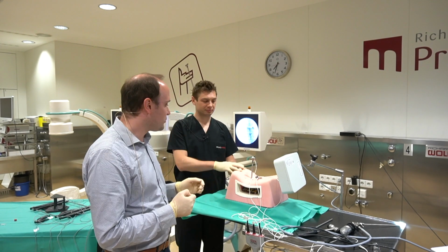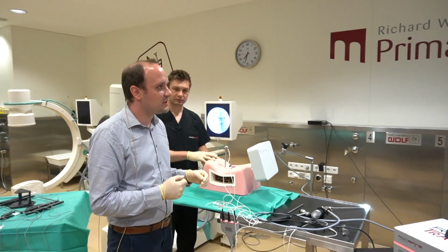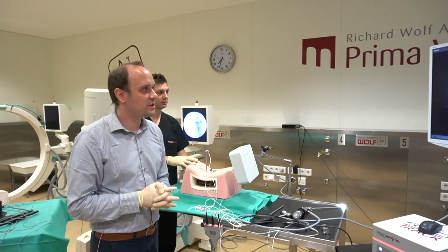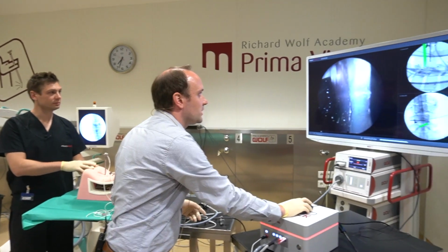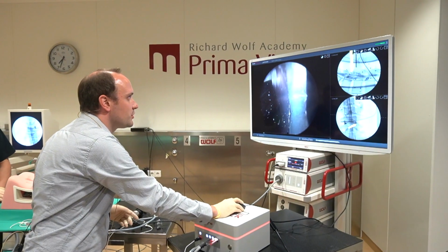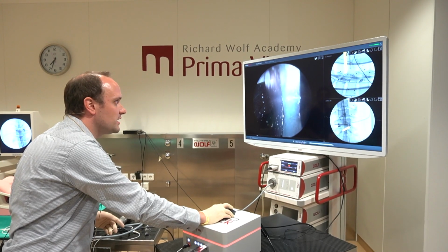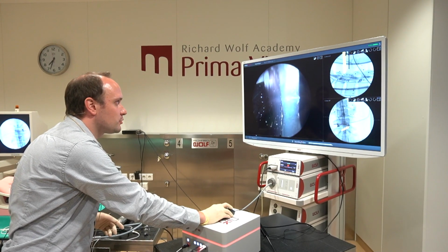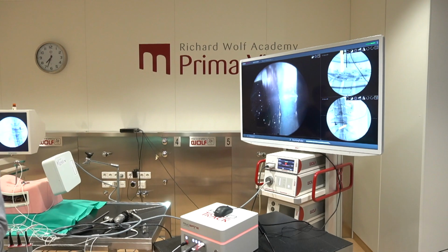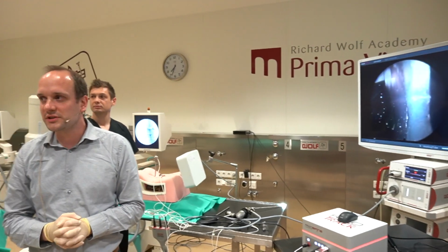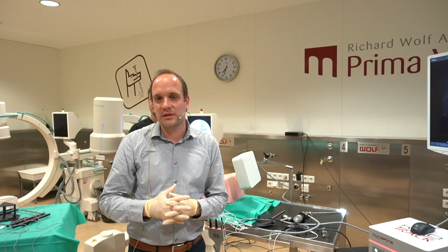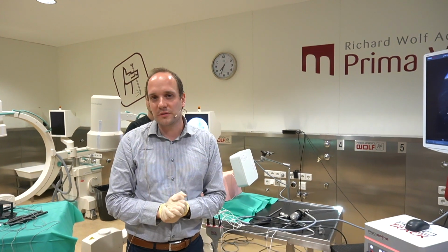The other way you can check the accuracy is the overlay during the patient registration. During the patient registration, we saw a yellow overlay on the needle, on the K-wire trajectory, as well as on this screw that we have on the patient reference. That is a good point to estimate the accuracy. We usually lie within 1.5 millimeters of accuracy.